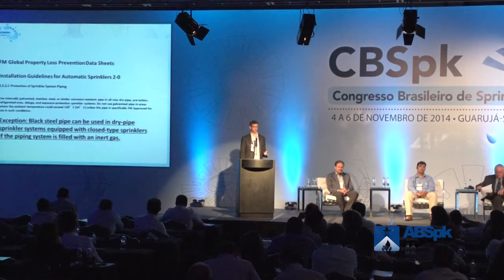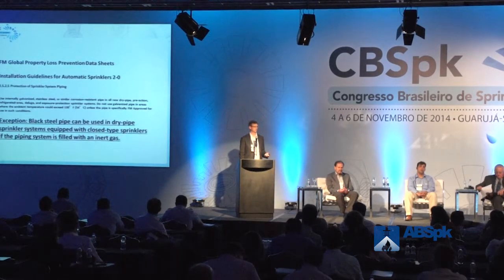Nitrogen has been around for a long time. FM actually recommends its use in certain applications. What we see in some of their property loss data sheets is that they say you can actually use black steel with nitrogen, because what nitrogen essentially does is take away the corrosion potential.